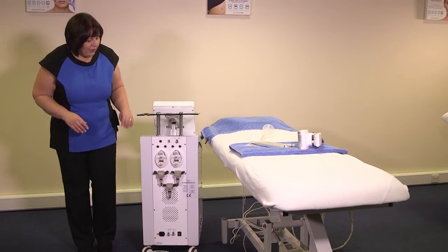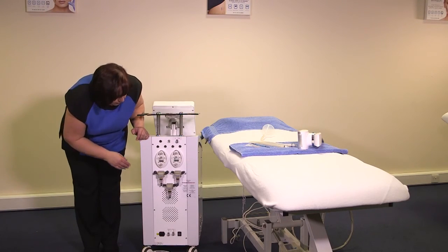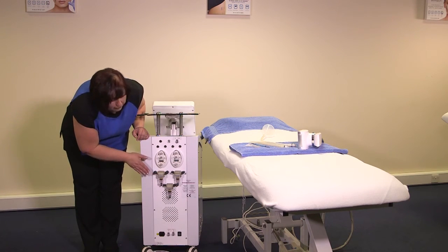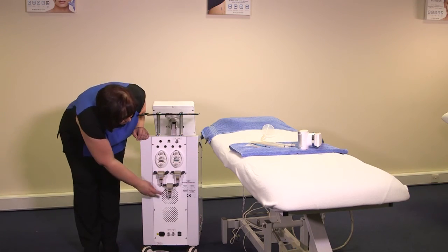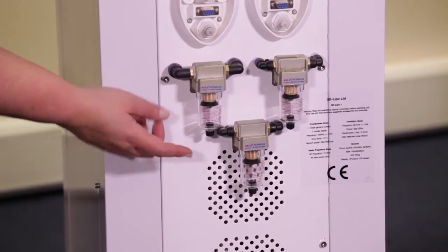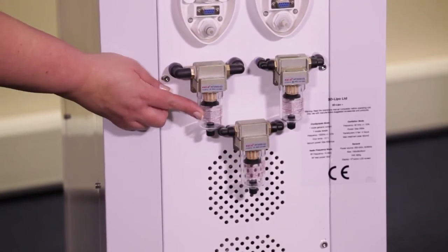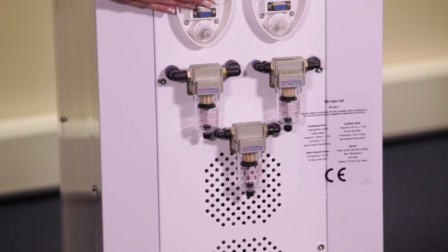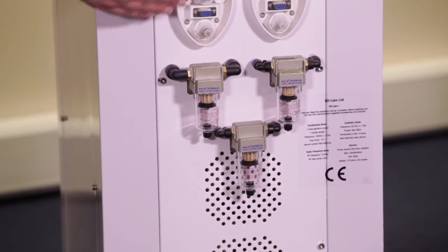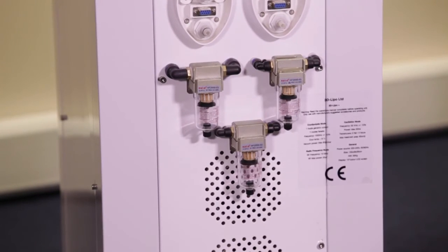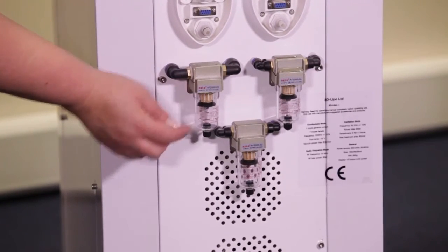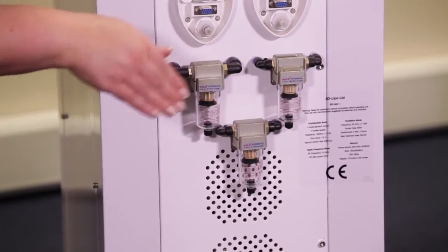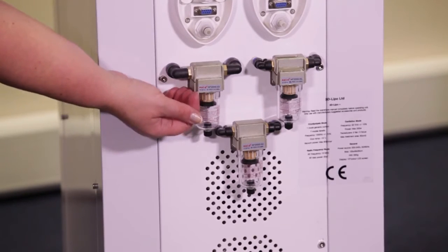When looking at the back of the unit, the things that you need to pay attention to, first of all, are the filters at the back. The Lipo Med has 3 filters for every vacuum outlet, whereas the Lipo Plus will have 1. You need to make sure every day that these filters are clear. If they have fluid in them, it will be from the cryo solution from the vacuum attachment or possibly from the vacuum roller. If you do see fluid in the filter, you need to unscrew the filter all the way down, empty it out, dry it, and then put it back in.